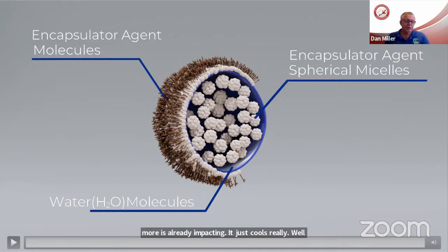At 1%, it cools 4 to 6 times greater than plain water. At 3%, it's 10 plus times greater than plain water. We have different rates for different materials. Lithium-ion batteries is 3%, so whether you're in the fire protection world or the firefighting world, it's 3%.